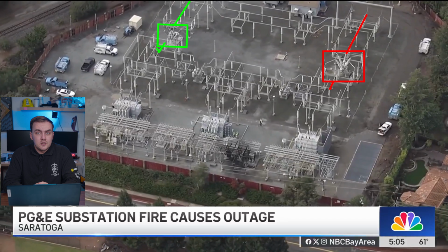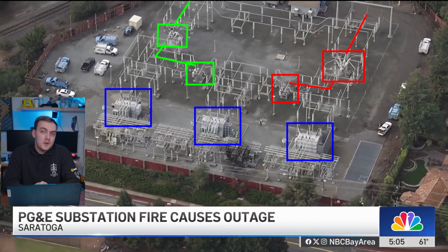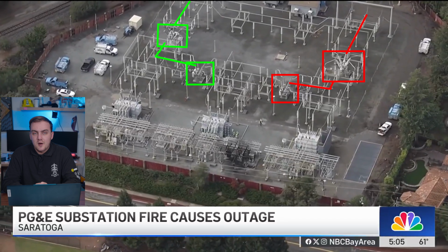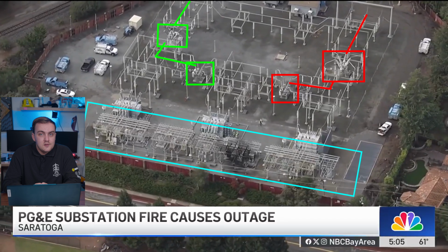Taking a step back to that T-junction on the bars again, we get two more circuit breakers here, which connect up our two circuits. Don't worry, I haven't forgotten about that bit at the top, and we'll come back to that in a second. So now we can see there's two circuits coming into the substation feeding three transformers. And because of that circuit breaker placement, we can feed any transformer from either circuit by opening or closing different breakers. It looks like each transformer also has a disconnector, so you can disconnect individual transformers once the circuit has been broken. It also looks like on the low voltage side, each transformer feeds the same bus bars, so you can take any individual transformer out for maintenance or for a fault, and still feed the same load from the remaining transformers. But the image is quite a mess and it's hard to say for sure, but it's not really relevant to the story.